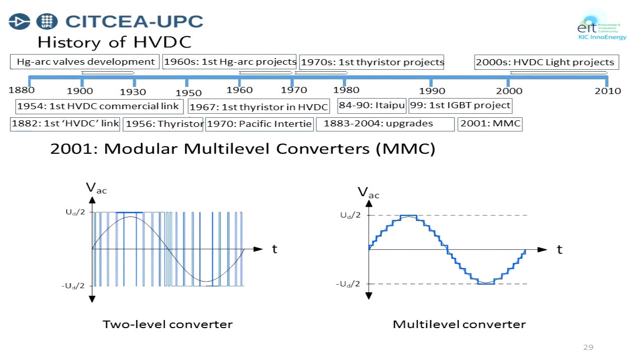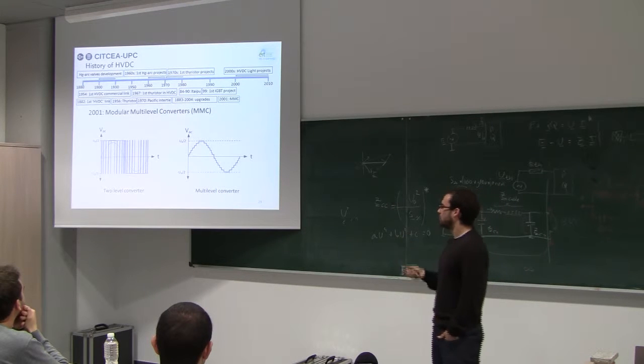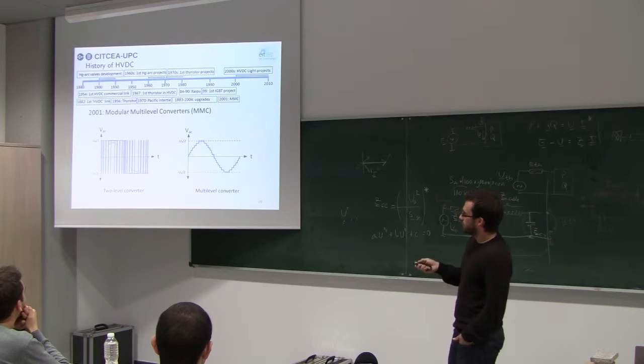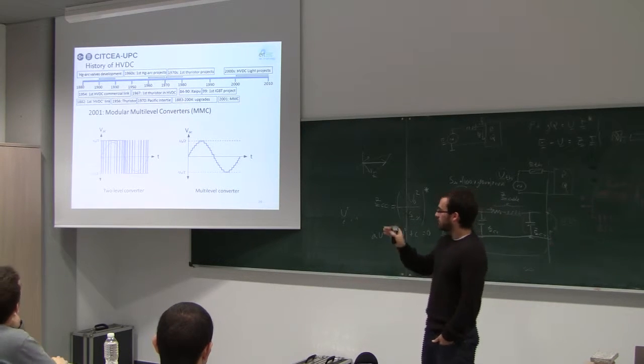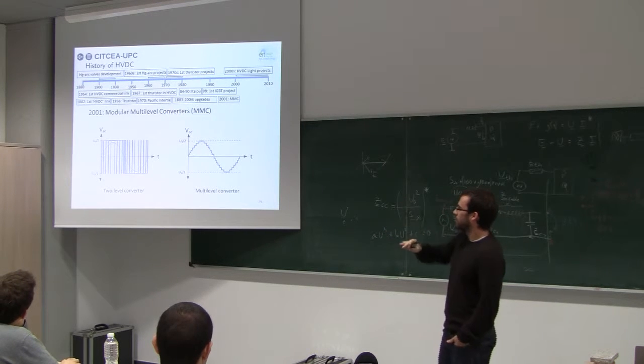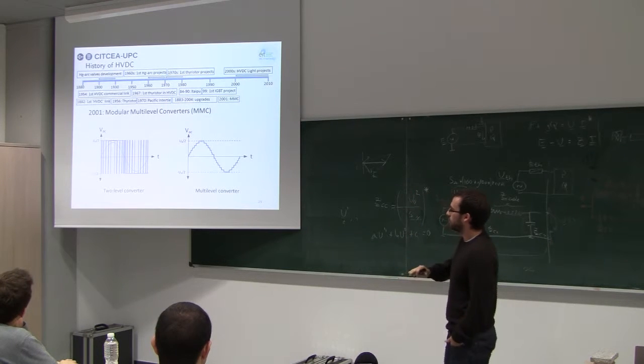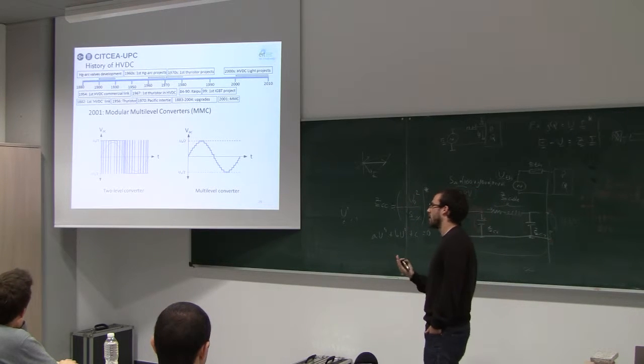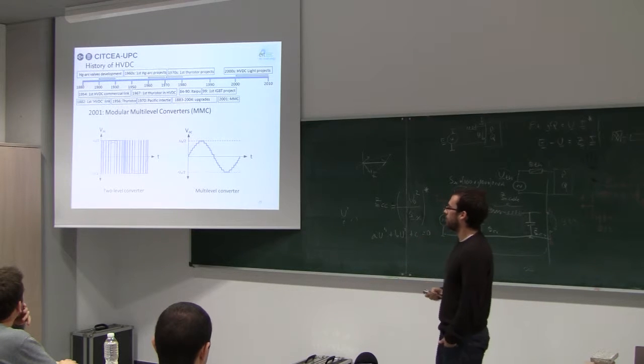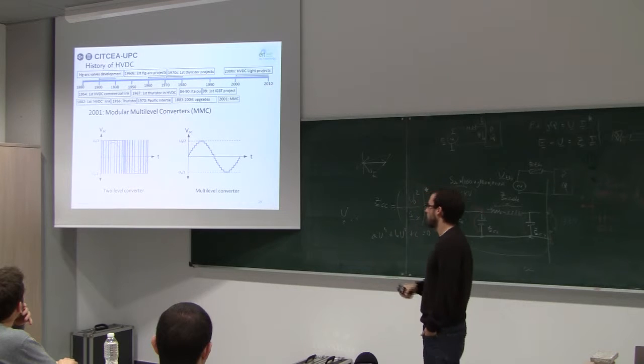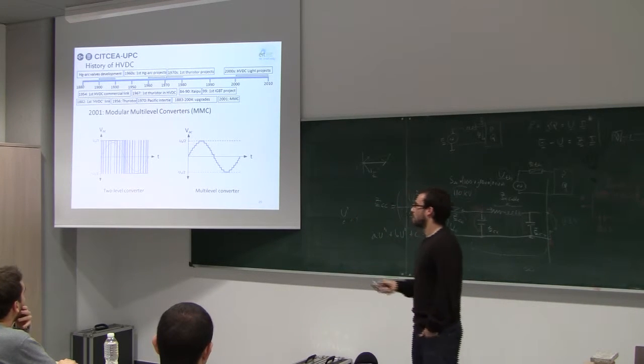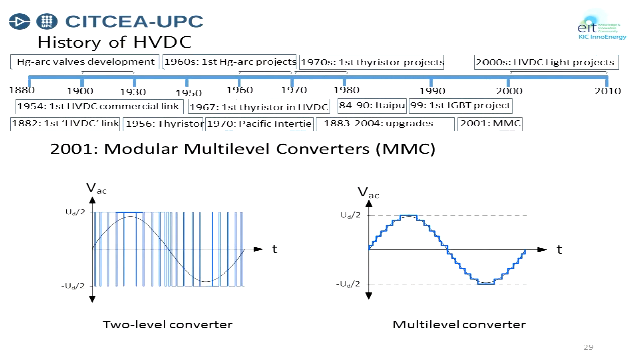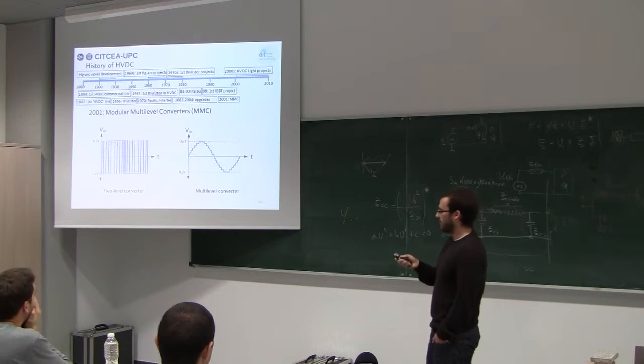In 2001, another VSC converter type, using many levels — what we call modular multilevel converters — was patented. In the image on the left side, we see how 2-level converters commutate: they have to go from maximum voltage to lower voltage, which causes greater stress to the converter and more harmonics. This advance, which Abel will talk about further later, allows filters to be reduced because you have fewer harmonics, but the control is more complex.